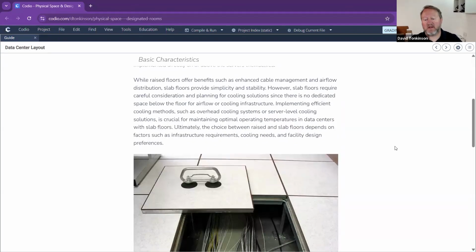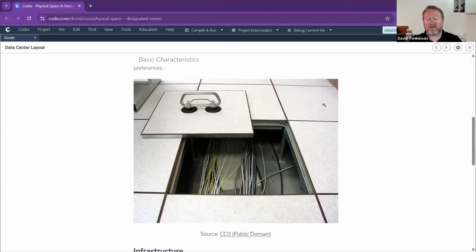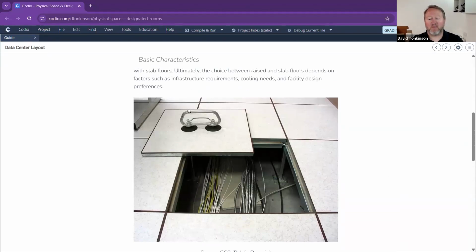Now, the benefit of this, looking at this picture, is that every single one of these slabs can be raised. Obviously, as soon as you start putting something on it, I think that's a desk leg there, it becomes a little bit trickier to raise. So you tend to keep clear paths through this. Your AC ones will simply have slots on the top, so they'll be grated, and these will go down the center of your cool aisles on your data center flooring. They can be lifted and moved if you need to access things for the air conditioning.